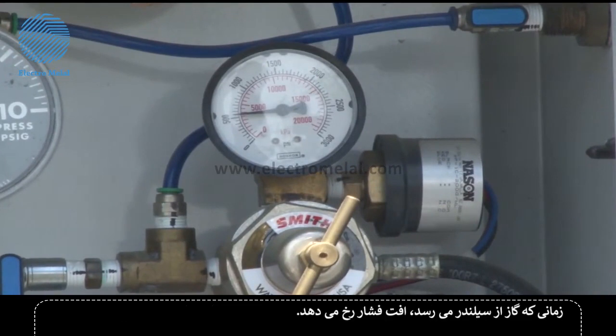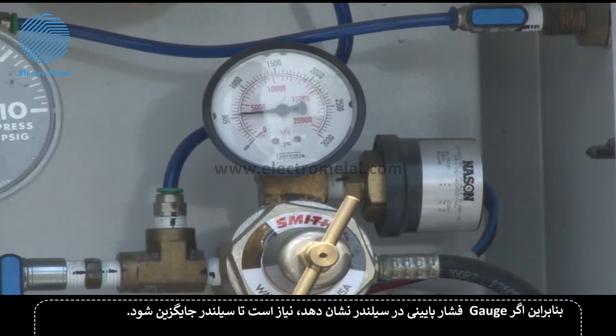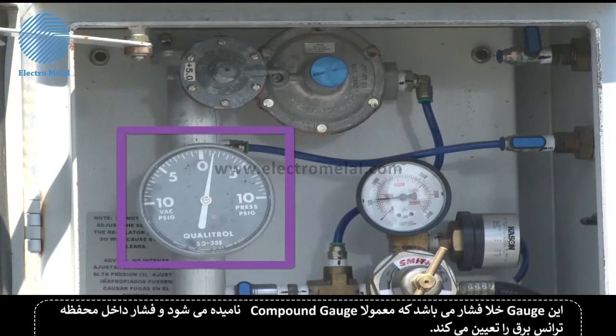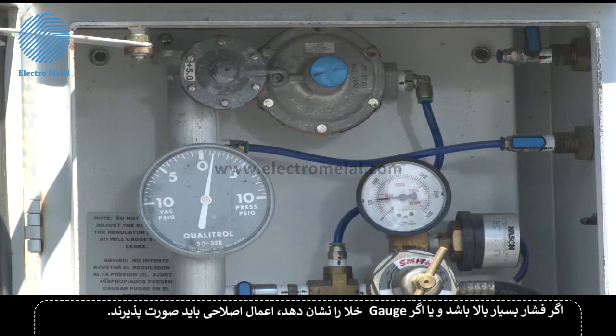As gas is taken from the cylinder, the pressure drops. So if the gauge indicates a low pressure, the cylinder may need to be replaced. This gauge is a pressure vacuum gauge, commonly called a compound gauge. It indicates the pressure inside the transformer enclosure. If the pressure is too high, or if the gauge indicates a vacuum, corrective action may have to be taken.